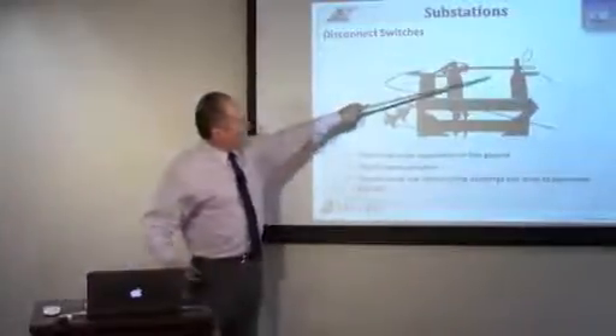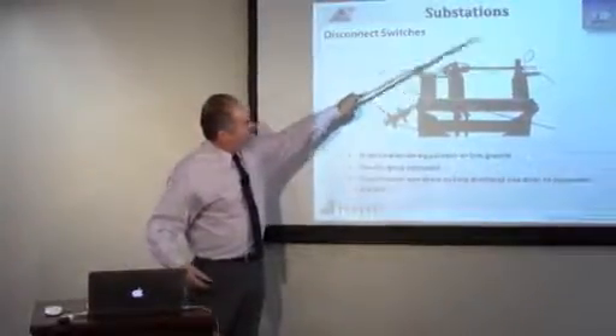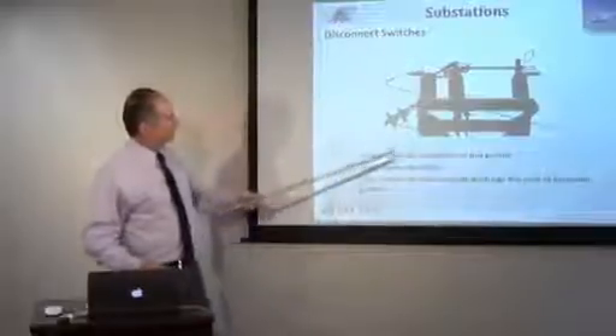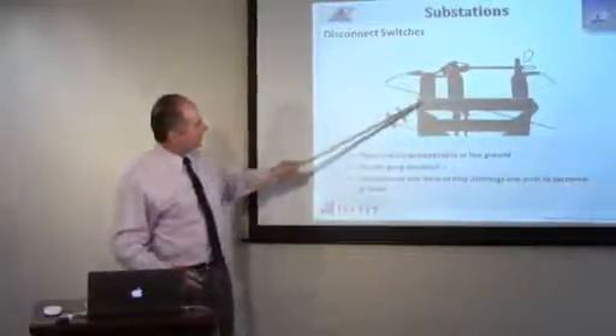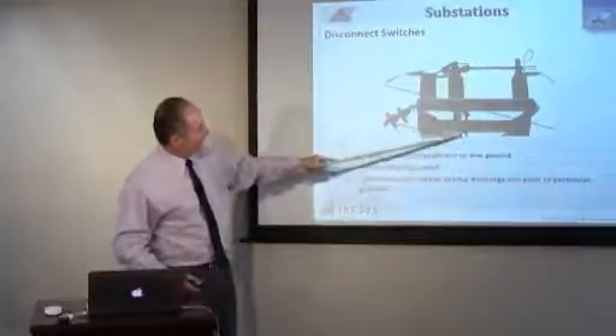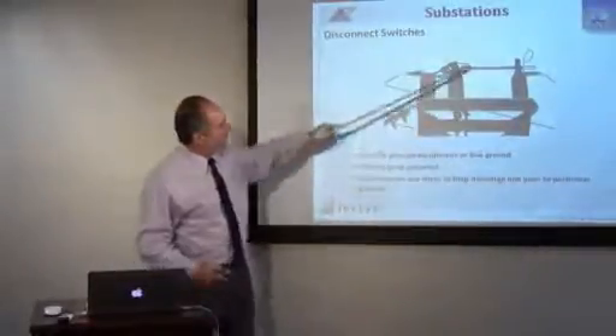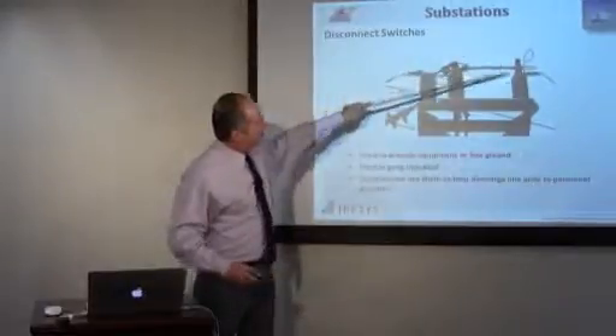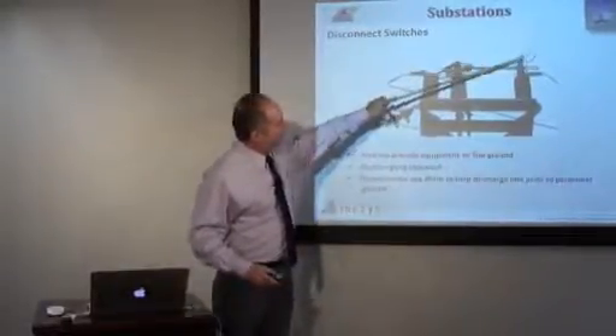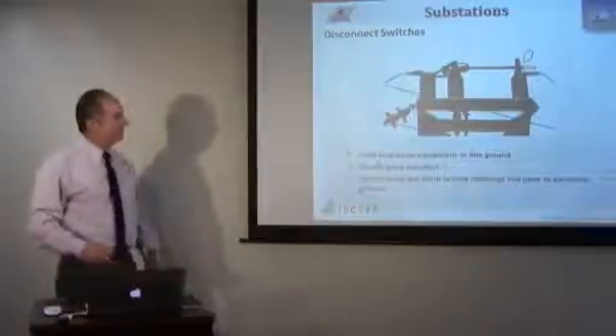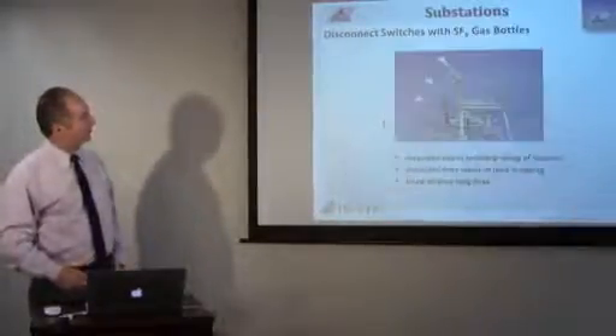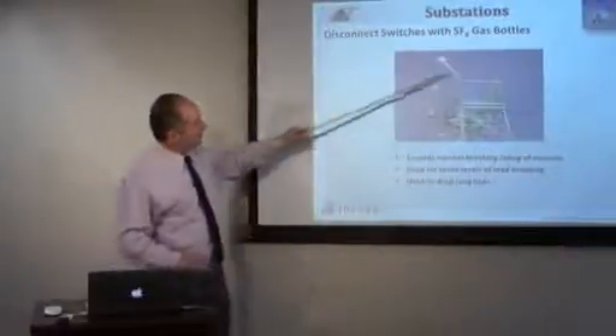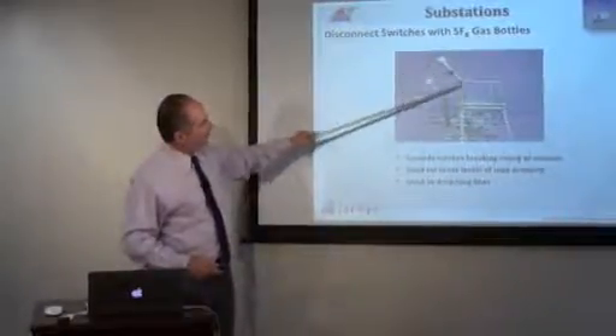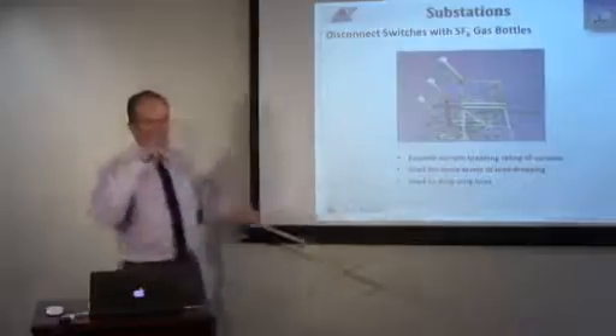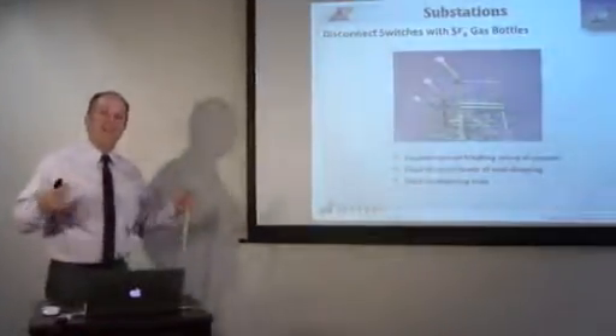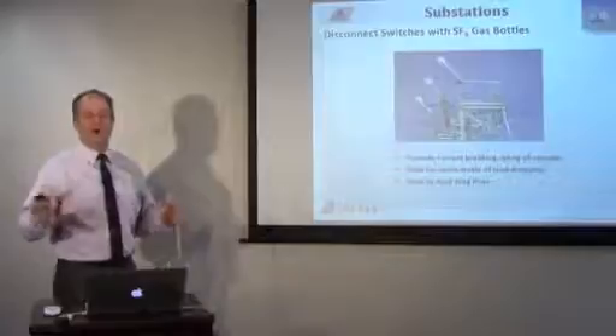Here's a vertical disconnect here. This switch goes up. You turn the control mechanism, which is down here. You can kind of see it. But when you turn that, this goes up, and this is an arcing horn trying to smooth out that arc. It's a vertical disconnect switch. Now this disconnect switch here has vacuum bottles associated with it. So when this switch opens, the arc is actually opening in a vacuum bottle, which allows you to open up some current.